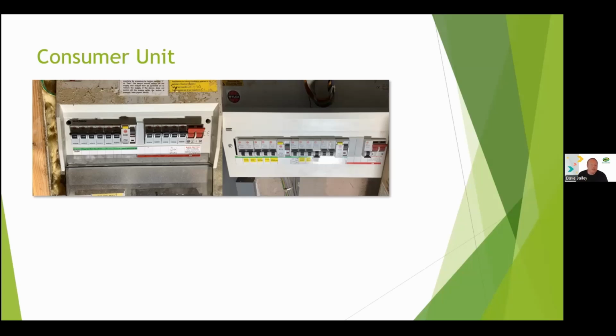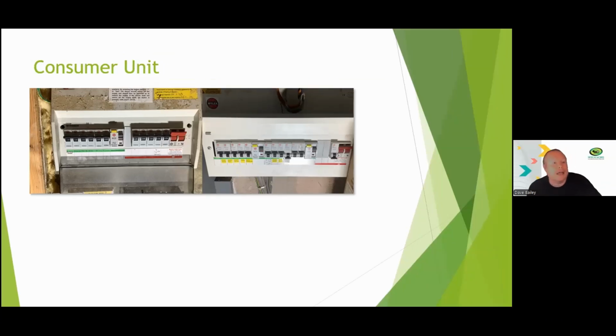An additional safety device - you can group some of these circuit breakers together and protect them all with an RCD. An RCD stands for residual current device, and that detects a current imbalance, so if anything strange is happening. Crucially, it has earth leakage protection, and this will prevent a shock by cutting off the power if it detects that the current is passing through something it perhaps shouldn't be passing through, for example, a human being. It realizes something's wrong and immediately shuts everything down, which is a great safety mechanism.